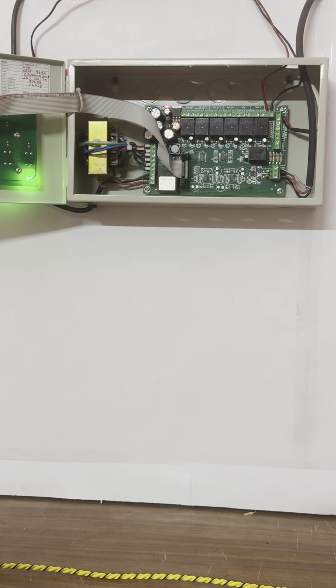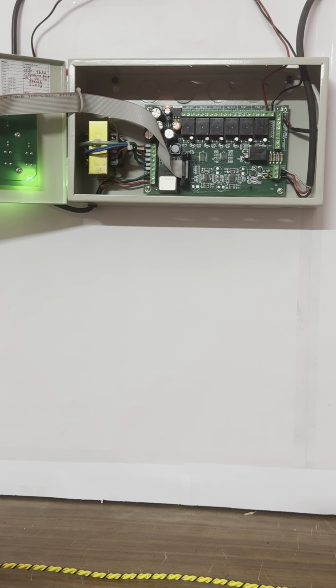So when you open the panel, you will be able to see the internal layout of the panel. The power cord is terminated here. 230 volt power is provided in the panel. The panel has terminals to connect the sensor cable. The legend is marked as zone 1, zone 2, zone 3 and zone 4. The sensor cable has to be connected to the zone 1 to zone 4 terminals. The sensor cable is non-polarized, it does not have any polarity for connection. So you can connect it either way, from zone 1 to zone 4.